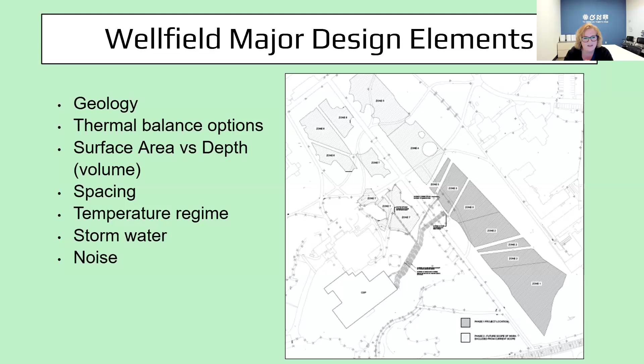We have 696 wells, 800 feet deep, each 8 inches in diameter, with a U-tube going down 800 feet and back up 800 feet, then grouted in. They're set on a 17-foot equilateral triangle grid pattern, which let us reduce the size compared to a typical square pattern.